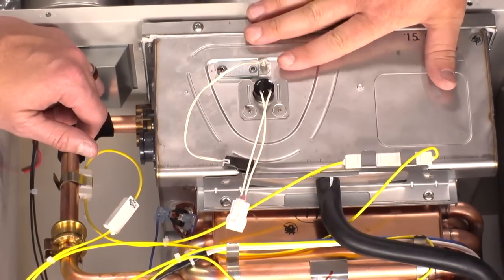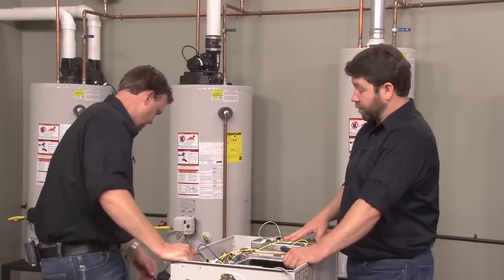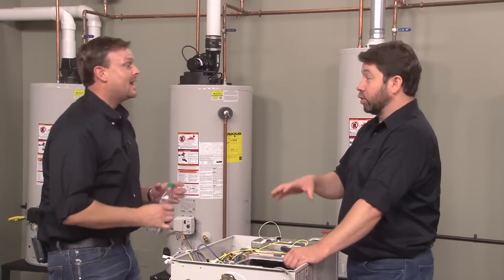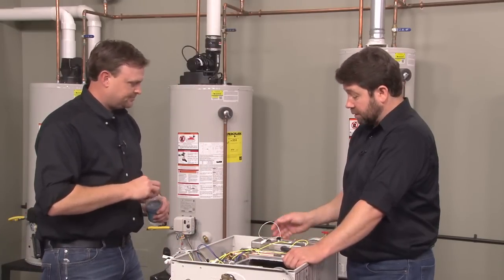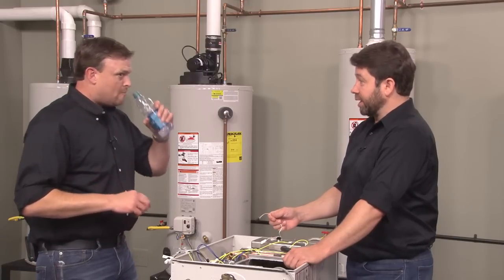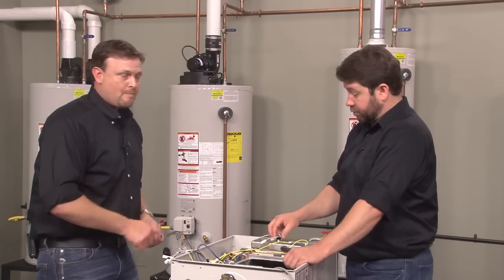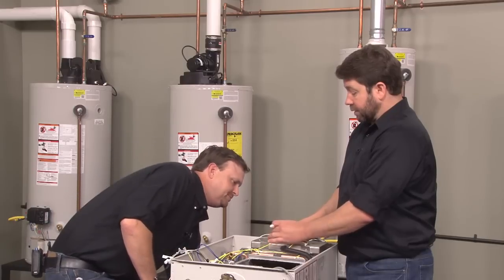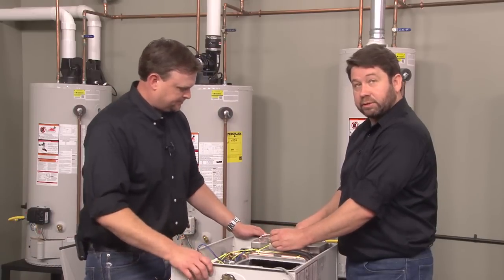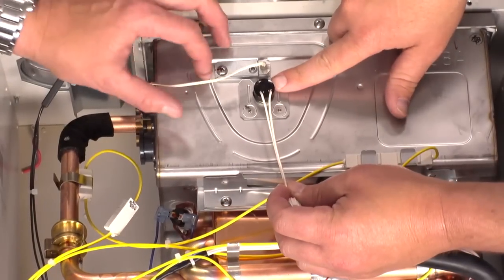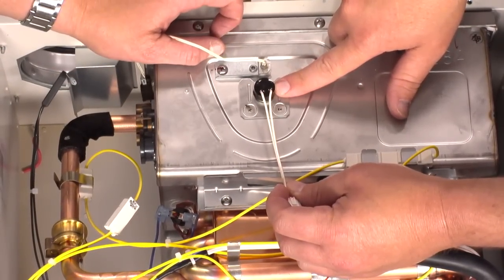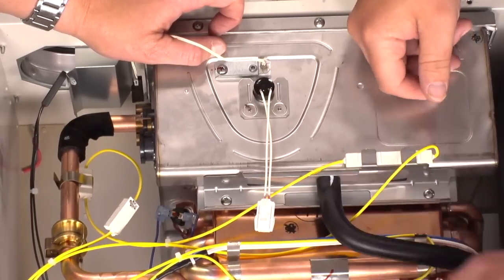If it sees temperatures that start to creep above 140, it will derate and try to lower those temperatures to save the venting. If for some reason this wasn't reading accurately and we had those higher temperatures, the exhaust high limit here, there we go, actually opens at 149 degrees, and it shuts down the gas valve.